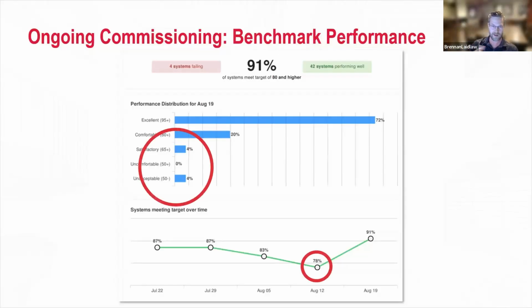This is a report run for 46 offices. When it was analyzed, 42 of them, or 91%, are doing well. So just as a simple checks and balances and benchmark, analytics can be used to quantify actual temperature performance and comfort in a building. And it can be used as a tool for optimization because you can track and trend that key performance indicator over time.